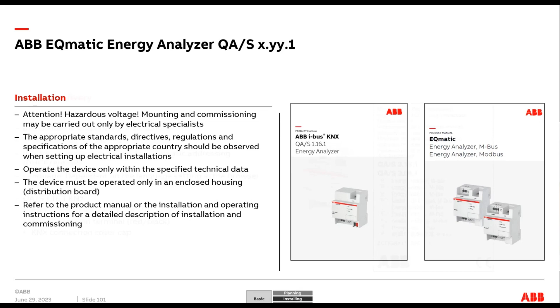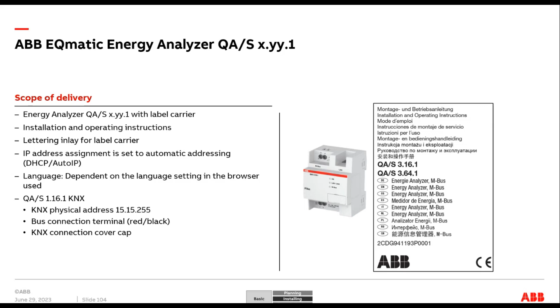In the box, of course, we have all the usual stuff. We take the device out of the box. We've all the installation instructions, etc. Remember as well that the device is set to DHCP automatically once it's pulled out of the box. So you stick it onto a normal network, it will give itself an IP address straight out of the box. Also remember, it's a KNX device, so our factory KNX device address is 15.15.255. So you will need to give it a device address on your network and download the application to it.